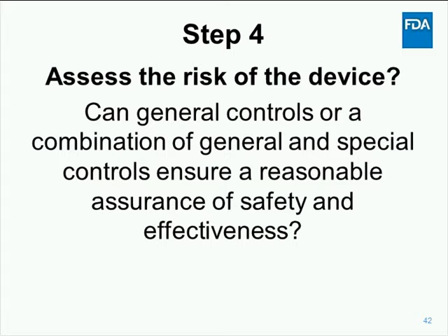We recommend you do the best you can with a device search for similar devices, but in order to get FDA's preliminary assessment of whether the FDA considers the de novo pathway as an appropriate pathway, you can also submit a request for a formal determination regarding whether the de novo process is appropriate. You do this through a 513(g) request. This provision states that FDA has a 60-day window to provide a determination regarding the classification and regulatory requirements applicable to a given device.